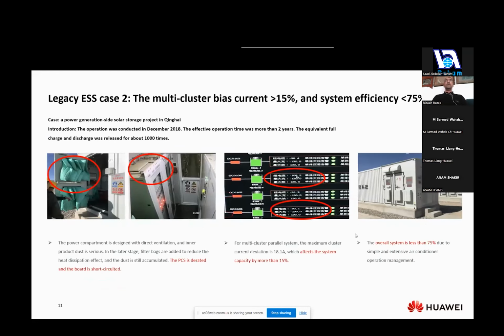The other factor is the multiple clusters of bias current. If multiple batteries are interconnected, as you can understand, the values will all differ as they are connected to the PCS. What you can see on the slide here is a project in China where a containerized 40-foot container was implemented, and the effective operation time was more than 2 years, equivalent to a full charge and discharge released around 1,000 times.